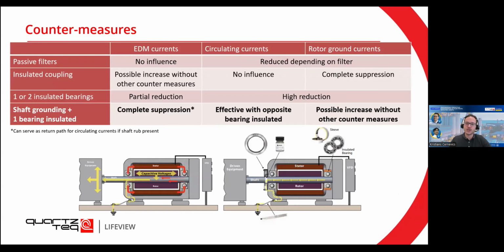Also, on most machines, there are already some countermeasures introduced. So you can have passive filters to eliminate the external voltage. You can insulate the coupling between, for example, the driven equipment and your rotating machine. You can insulate some of the bearings, but the most effective, I think, at this moment, and probably the industry standard, is shaft grounding.